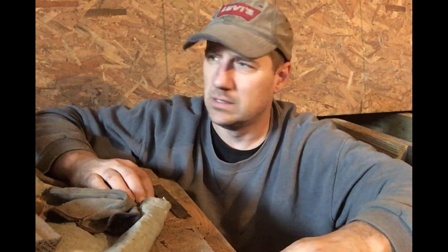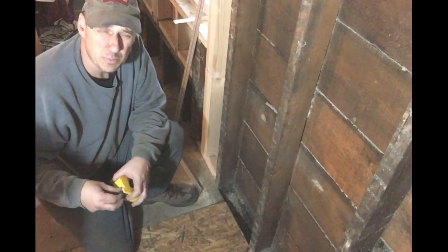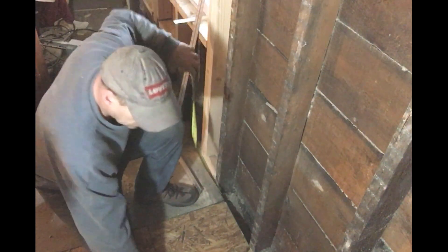So it's clear. Hopefully I only need to go down one more time to pull some wire — that's probably what I should do now. So I'm going to start putting in some outlets. First thing I need to do is hang a duplex receptacle box. Those generally are about 16 inches off the floor to the top of the box.